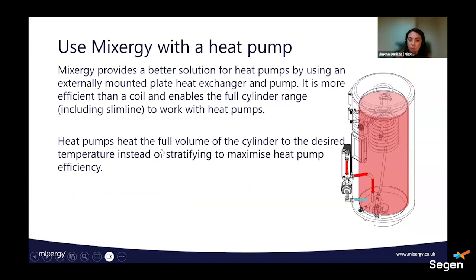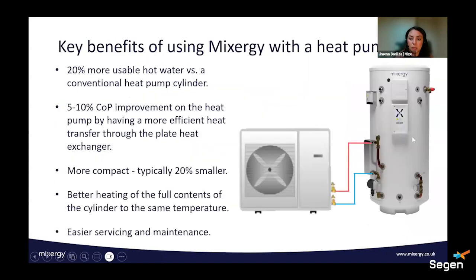So the difference when you use it with a heat pump is that you will heat the full volume of the cylinder to the desired temperature. And this is to maximize the heat pump efficiency. That's one of the key things that are different. The benefits are that there's 20% more usable hot water versus a conventional cylinder. There's a 5 to 10% COP improvement on the heat pump. It's more compact, typically 20% smaller. Better heating of full contents of the cylinder to the same temperature, and easier servicing and maintenance.